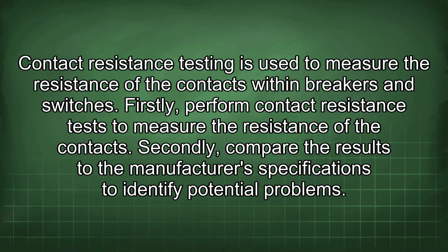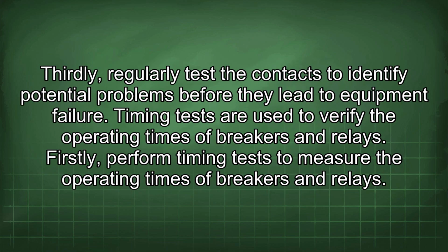Contact resistance testing is used to measure the resistance of the contacts within breakers and switches. Firstly, perform contact resistance tests to measure the resistance of the contacts. Secondly, compare the results to the manufacturer's specifications to identify potential problems. Thirdly, regularly test the contacts to identify potential problems before they lead to equipment failure.